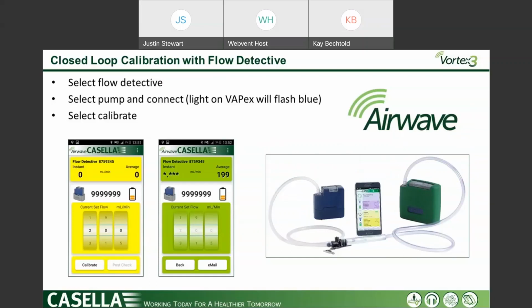And then when you're using the Flow Detective, the way that works is you set your flow rate, you hit calibrate, it turns from yellow to green. And then once it's completed, you send yourself an emailed report, and it almost stamps it for your pre and your post calibration. That's it. I don't know how to make it much simpler. So we tried to make things just simple, just like how the pump works. You set the flow rate, you press calibrate, and you're done.